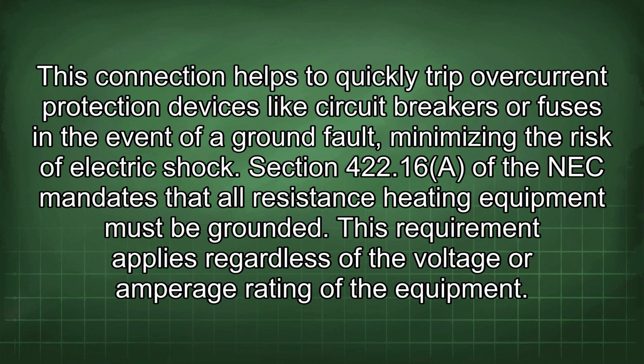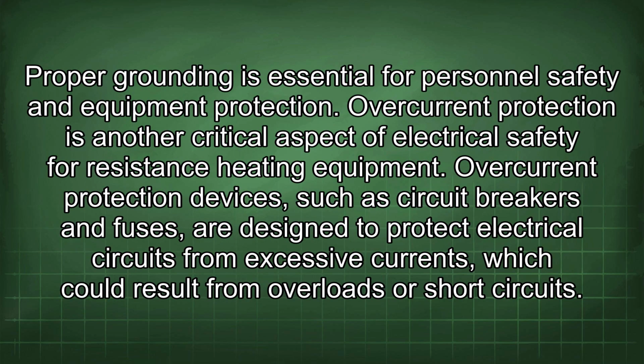Section 422.16 of the NEC mandates that all resistance heating equipment must be grounded. This requirement applies regardless of the voltage or amperage rating of the equipment. Proper grounding is essential for personnel safety and equipment protection.